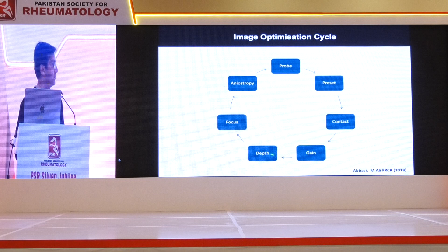Now, in musculoskeletal imaging and with linear probes, this is a real problem. When you're imaging something that's parallel, the sound waves should be going down the probe and then reflecting back 90 degrees back to your probe again. If you are imaging a structure that's at angles, so that might be because of a vessel or a bone or a finger, then some of the sound waves that are sent out are reflected but not caught by the beam. And what the machine interprets that as is that this must be a structure that doesn't reflect sound, or that transmits the whole sound, so it fills in the gap with black.